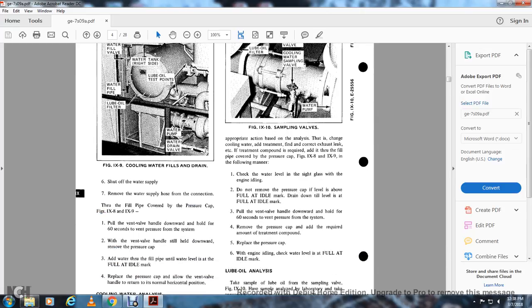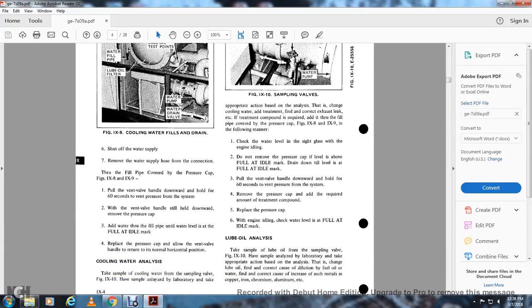Shut off the water supply. Remove the water supply hose from the fill pipe connection, then replace the pressure cap (figures 9-8 and 9-9). To use the second method: pull the vent valve handle down for 60 seconds to vent pressure from the system. With the vent valve handle still held down, remove the pressure cap and add water through the fill pipe until the level is at the full idle mark. Replace the pressure cap and allow the vent valve handle to return to the normal horizontal position.